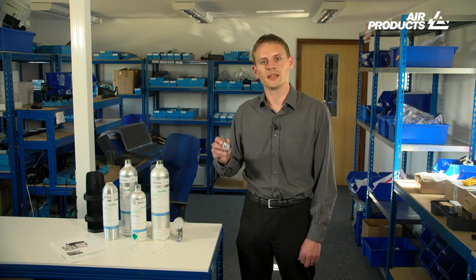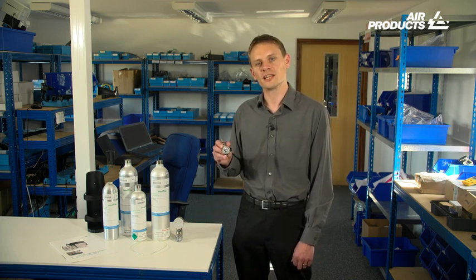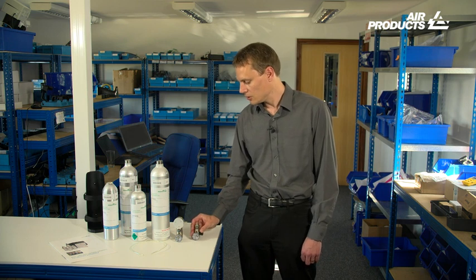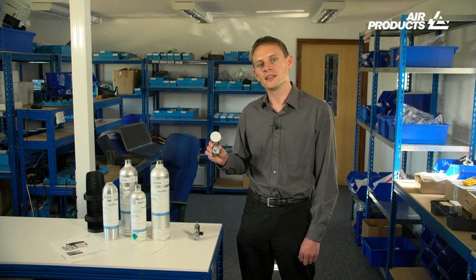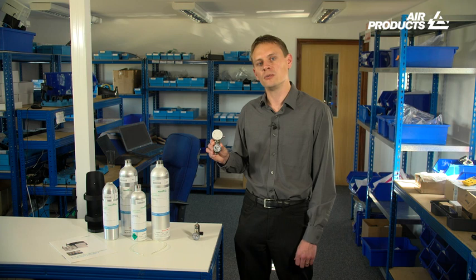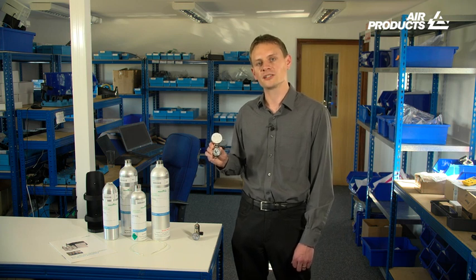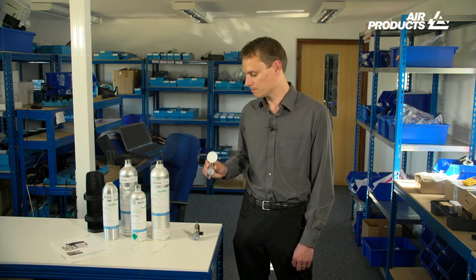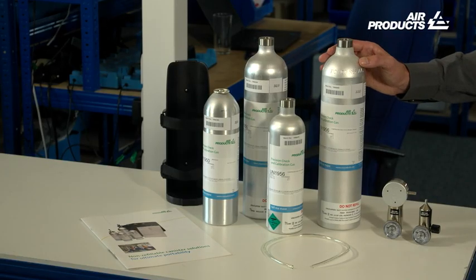The instrument manufacturer will normally recommend the optimum flow rate of gas needed in their operating procedures. Selecting a suitable fixed flow regulator, like this, will maximise the number of tests possible. Using a demand flow regulator like this for instruments fitted with internal pumps further optimises the process. These units limit the flow of gas to that demanded by the instrument and means there is no wasted gas. The largest canisters hold about 110 gas litres.